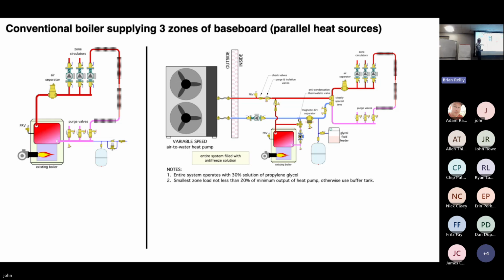And I put down: entire system operates with 30% solution of propylene glycol. And I also put down: small zone not less than 20% of minimum output of heat pump, otherwise use buffer tank. Variable speed heat pumps can go down to roughly about 25% of the rated capacity. So as the zones are turning on and off, that heat pump would adjust its compressor speed, just the way a modulating boiler will adjust its burner operation.